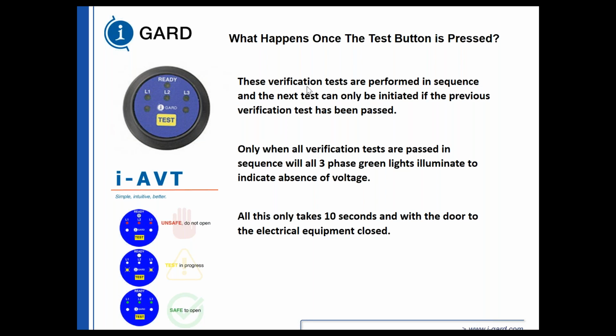So all the verifications are done in a sequence. It takes much less time than it used to before. 20 seconds, it's done. Only when all verification tests have passed, the 3 green LEDs illuminate. It takes about 10 seconds; I said 20 seconds because it probably takes you about 5 seconds to find the button.